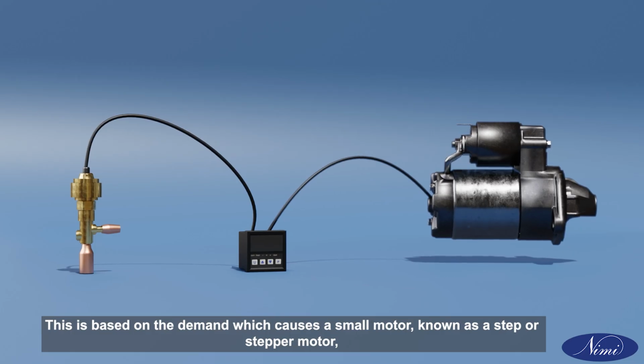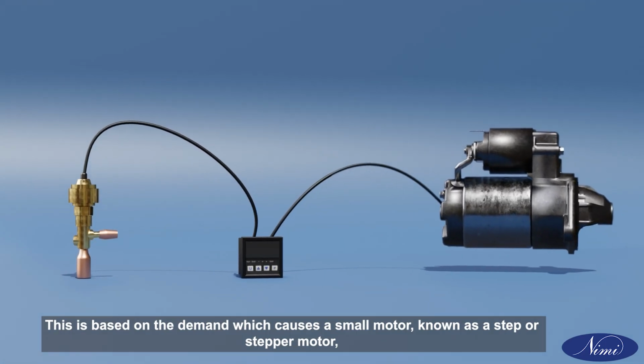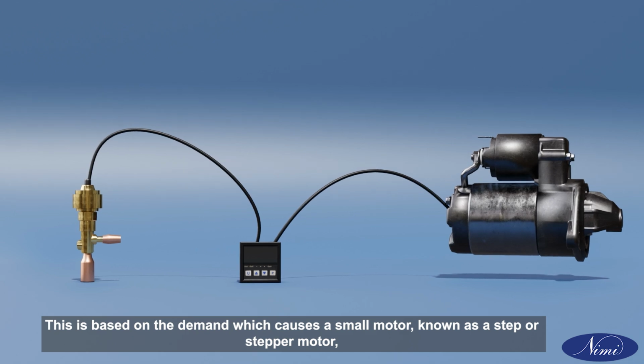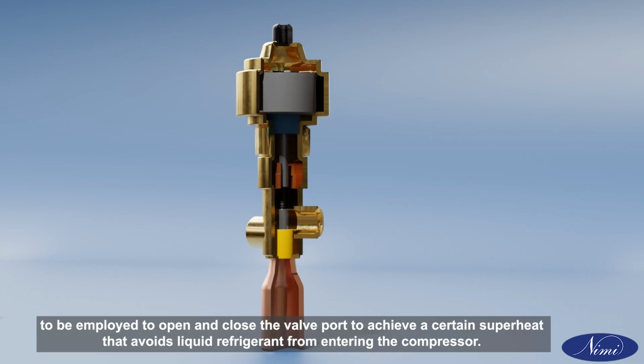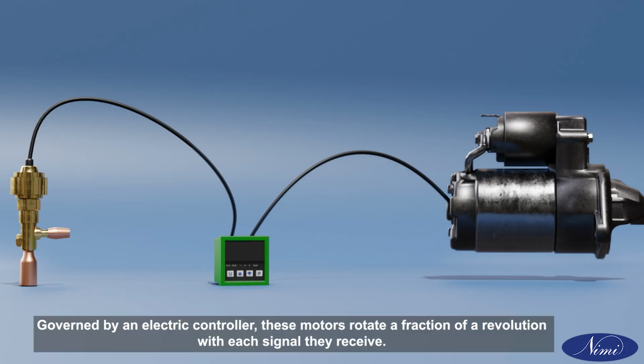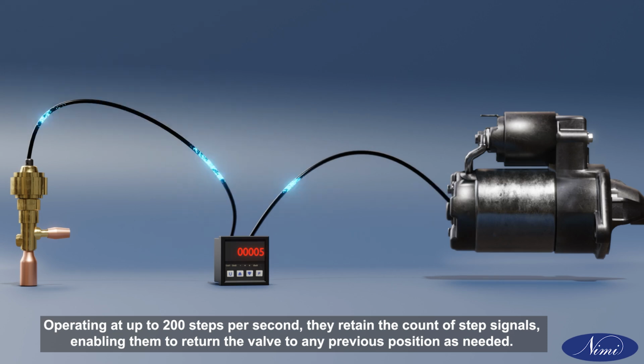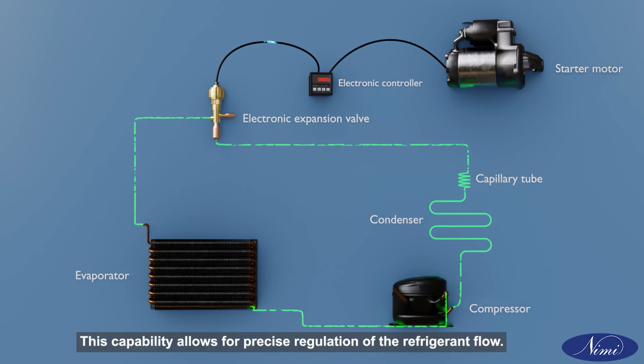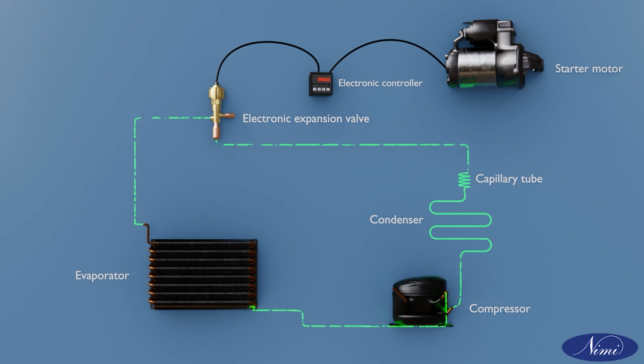evaporator? This is based on the demand, which causes a small motor, known as a step or stepper motor, to be employed to open and close a valve port to achieve a certain superheat that avoids liquid refrigerant from entering the compressor. Governed by an electric controller, these motors rotate a fraction of a revolution with each signal they receive. Operating at up to 200 steps per second, they retain the count of step signals, enabling them to return the valve to any previous position as needed. This capability allows for precise regulation of the refrigerant flow.